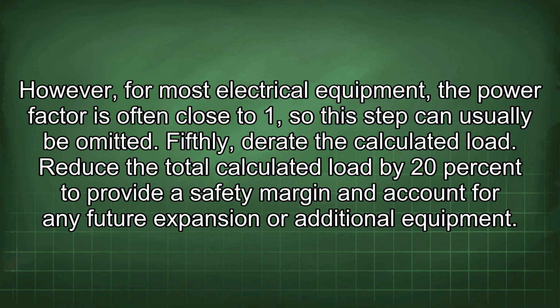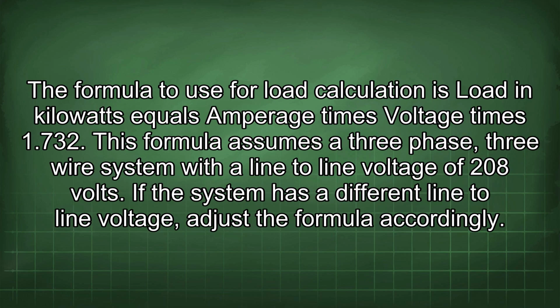Fifthly, derate the calculated load. Reduce the total calculated load by 20% to provide a safety margin and account for any future expansion or additional equipment. The formula to use for load calculation is load in kilowatts equals amperage times voltage times 1.732. This formula assumes a three-phase, three-wire system with a line-to-line voltage of 208 volts. If the system has a different line-to-line voltage, adjust the formula accordingly.